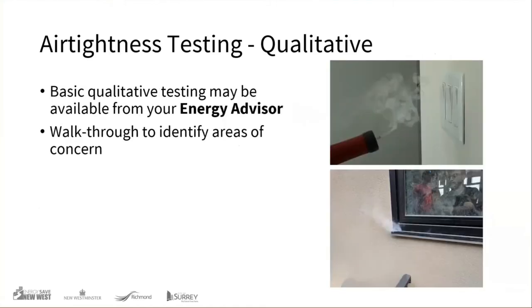As part of this mid-construction test, we also want to do qualitative testing — not just the number, but using a visual indicator for air tightness. Our approach uses an industrial fog generator to see where smoke is coming out. It could also be a vape device or incense sticks: with the fans on you can see the smoke flow through the enclosure wherever there are discontinuities. Having it accessible so we can repair it right then — that's where the value of this testing comes in. Guidance is available in some of the BC Housing guides.